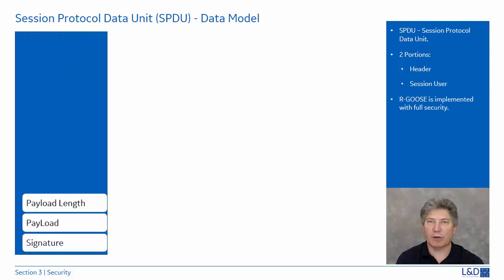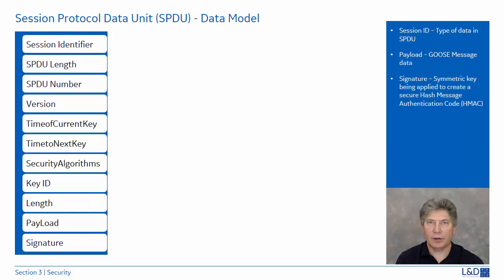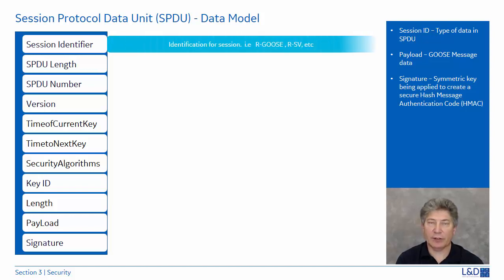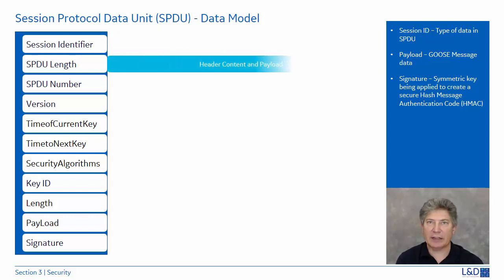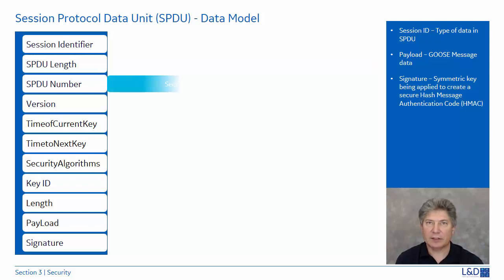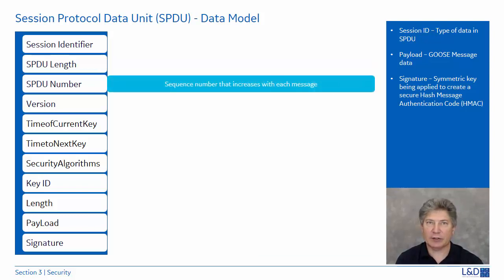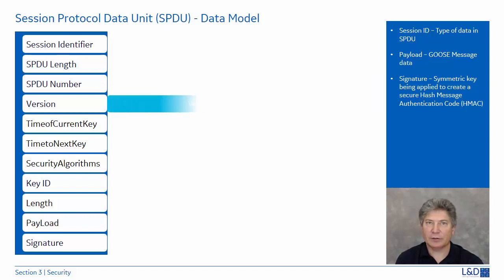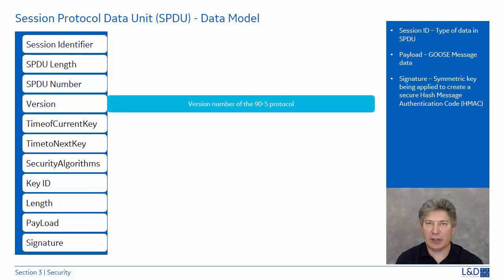Let's quickly review each part of the SPDU. The session identifier indicates what type of payload there is, whether this is a GOOSE or a sampled value. The SPDU length is the size of the SPDU, header content, and payload. The SPDU number is a value used to detect duplicates or out-of-order packets. This is maintained by the sender and starts with 0 and increments with each subsequent SPDU. The version is the version of the 61850-90-5 protocol that is being used.